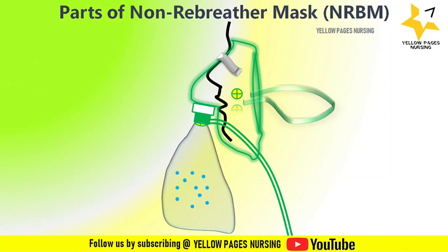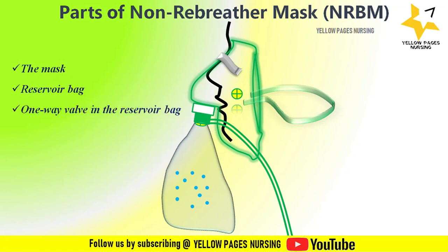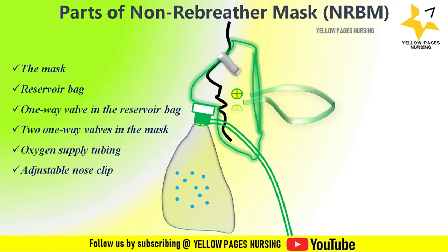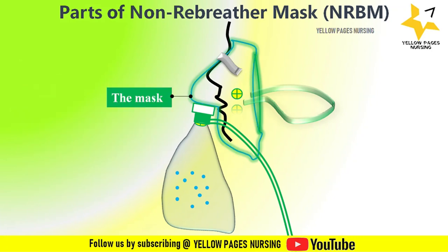The parts of a non-rebreather mask include: the mask, reservoir bag, one-way valve between the mask and reservoir bag, two one-way valves in the mask, oxygen supply tubing, adjustable nose clip, and elastic strap. The mask is generally made of soft, pliable plastic material which fits over the patient's nose and mouth. If you look at the picture, you can see how the mask looks — it resembles a normal oxygen mask.